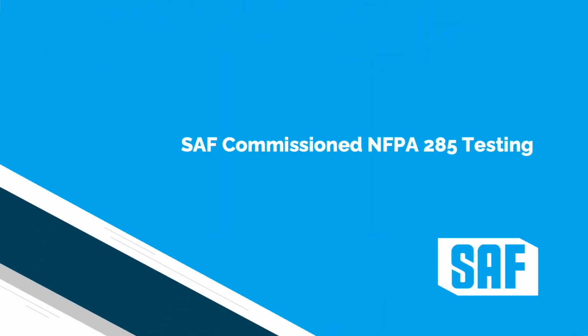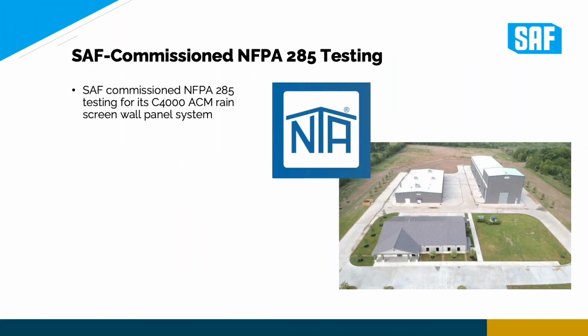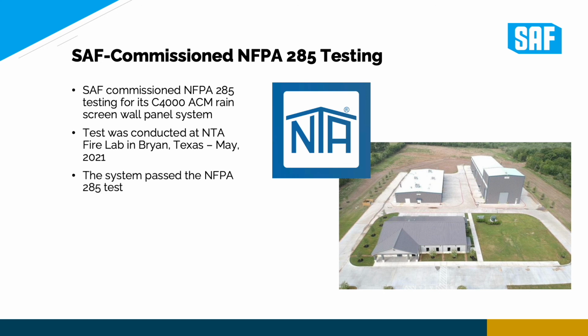That's why SAF has also commissioned its own NFPA 285 testing. SAF commissioned NFPA 285 testing using the SAF C4000 ACM rain screen system in a wall assembly. The test was performed at NTA Fire Lab in Bryan, Texas in May of 2021. As anticipated, the wall assembly passed the test.